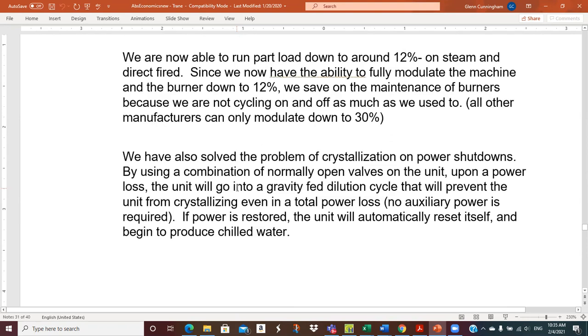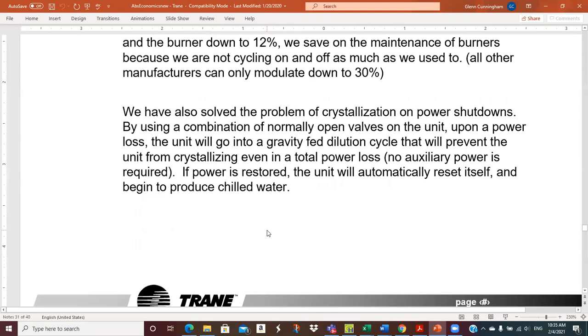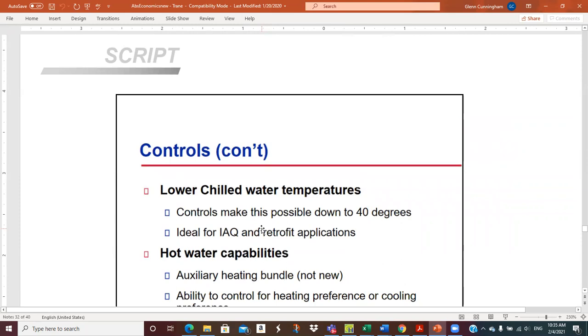We also solve the problem of crystallization on power shutdowns by using a combination of normally open valves on the unit. Upon a power loss, the unit will go into a gravity-fed dilution cycle that prevents crystallization. So that's pretty good. And as power is restored, the unit will automatically restart and begin. About improvements.